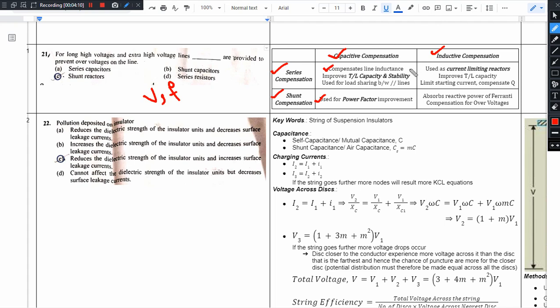Next, inductors. Inductors will act like current limiting reactors. Transmission line over currents we limit with the help of inductors, because inductors oppose the rate of change of current. So current limiting reactors, inductor we will place in series. And inductor will absorb the reactive power of Ferranti effect. Ferranti effect in light loaded lines. And here the high voltages or over voltages are somewhat related to this effect.